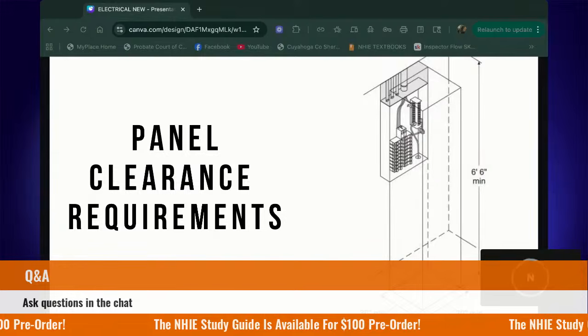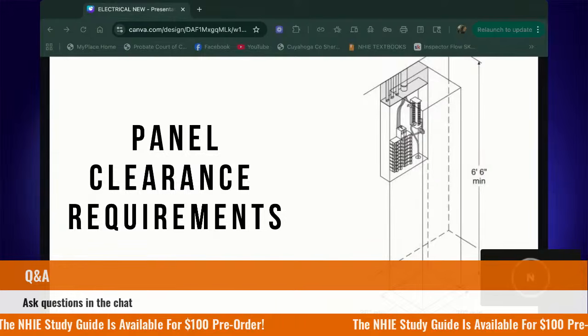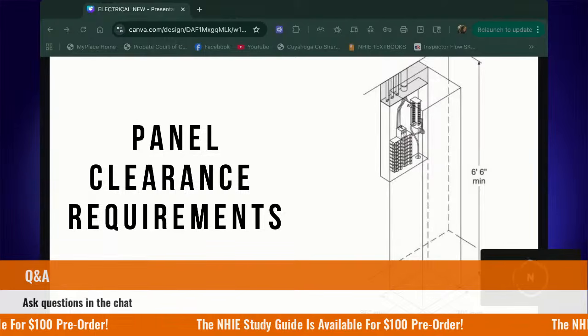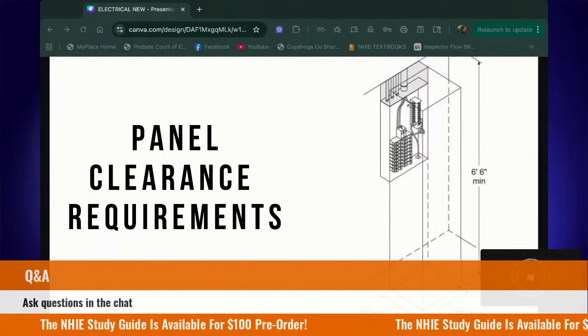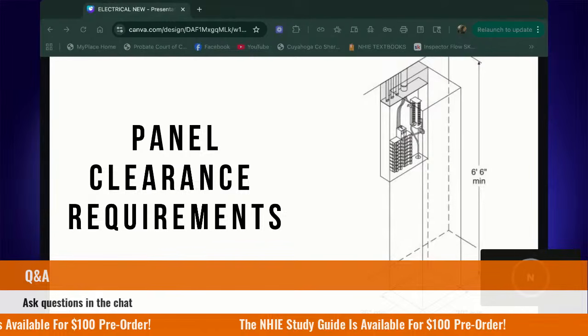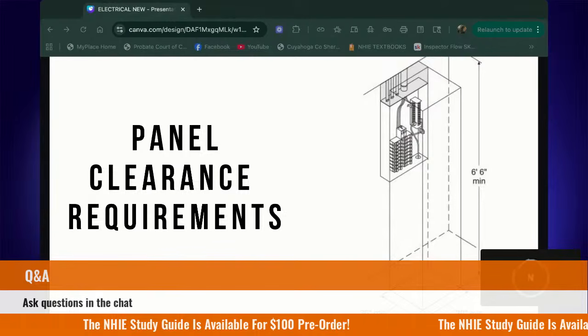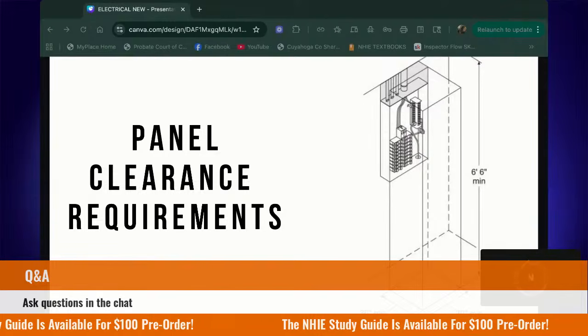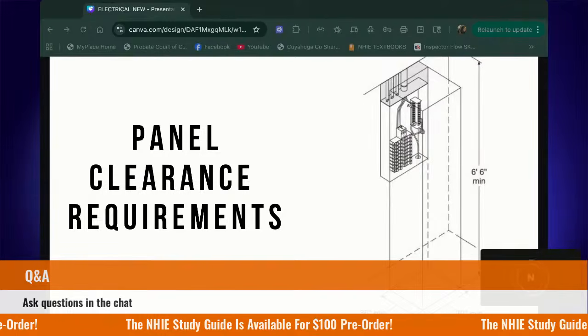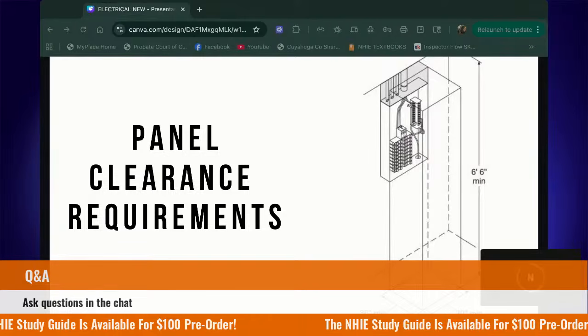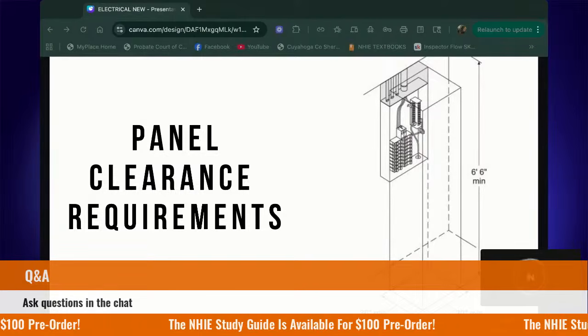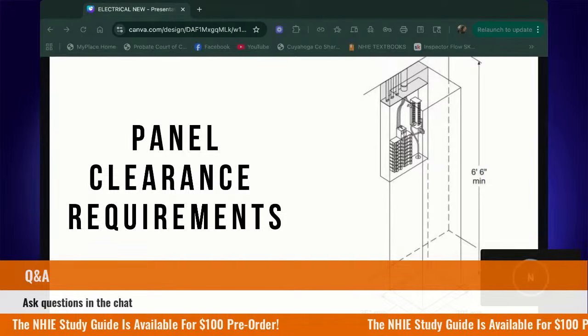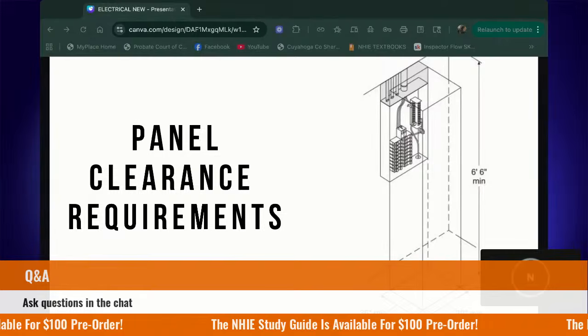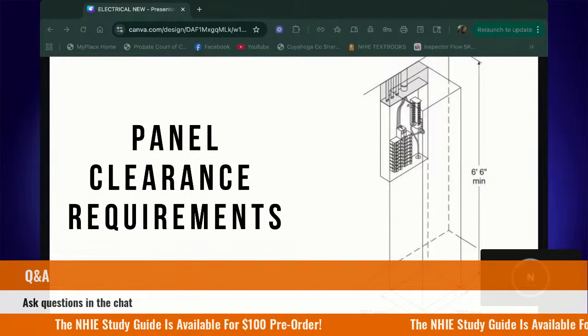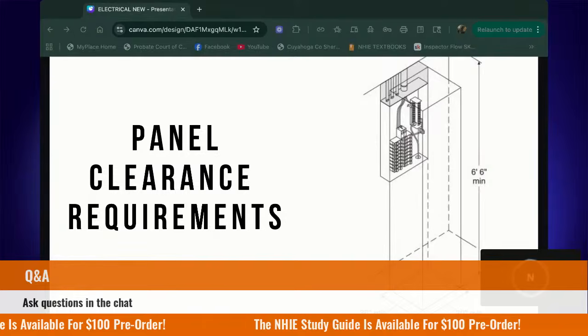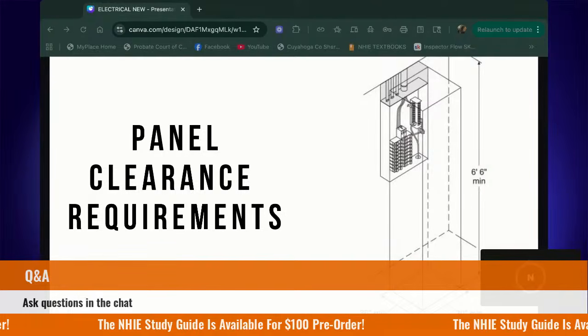So a lot of times for me, most times the panels are in the basements in old houses, and they're often leaky. Well, what if there's a water leak right at the front of the panel? Or what if there are signs that the panel itself has had moisture intrusion? Would you open it? No. I don't either. Now you have some people who would say they may try it. So again, these are some of the subjective decisions that you will have to make when you're out in the field, but it's important that you know the implications of both.